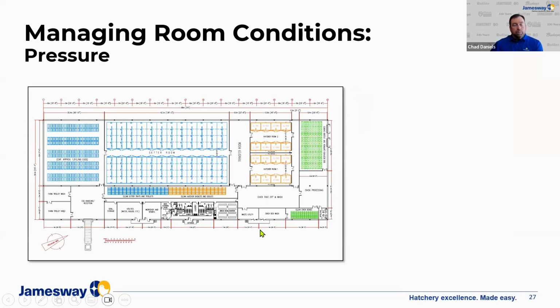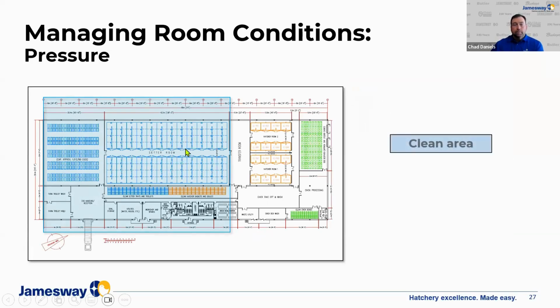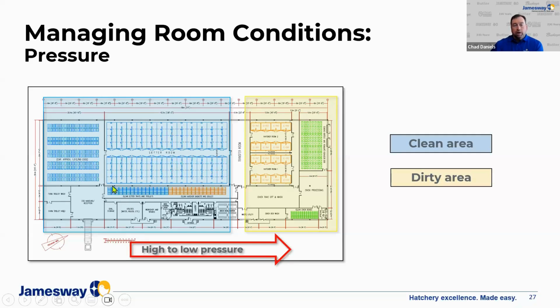The next step when we talk about pressure control is looking at it from a biosecurity standpoint. We look at this portion of the hatchery, this being egg receiving, egg room, and incubation. That is our clean area. And then the other end of the hatchery, where we have hatcher rooms, chick takeoff, and chick holding, is the dirty area. So from a biosecurity standpoint, when I look at my pressure settings, I want to make sure I have higher pressures on the clean end of the hatchery and lower pressures on the dirty end. I want to make sure clean air is always flowing in this direction.